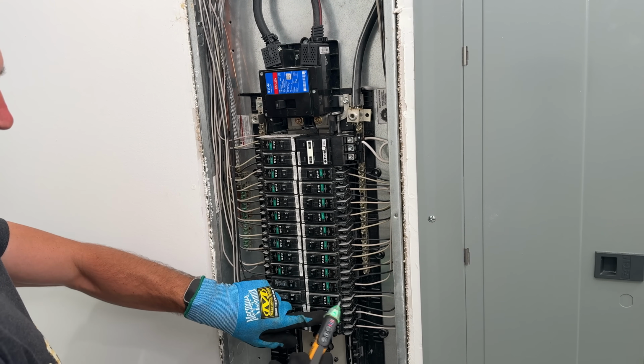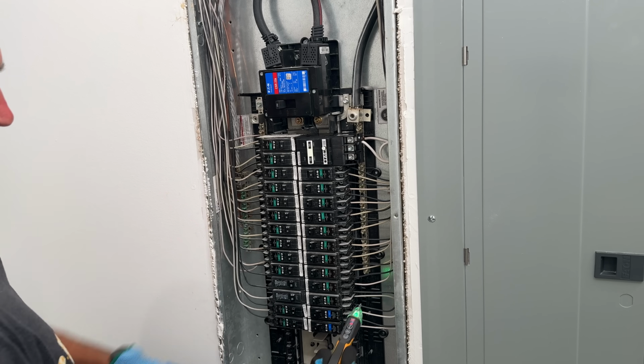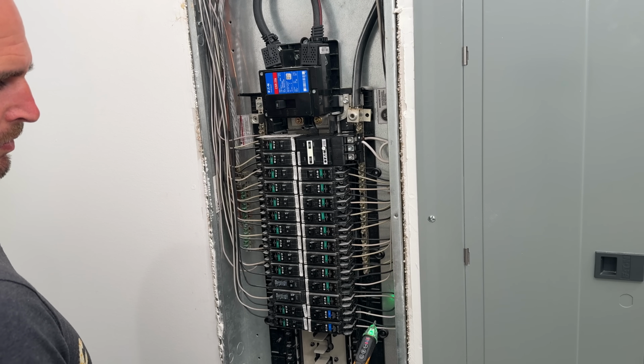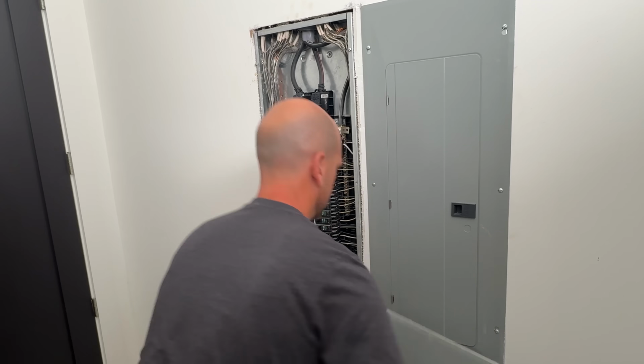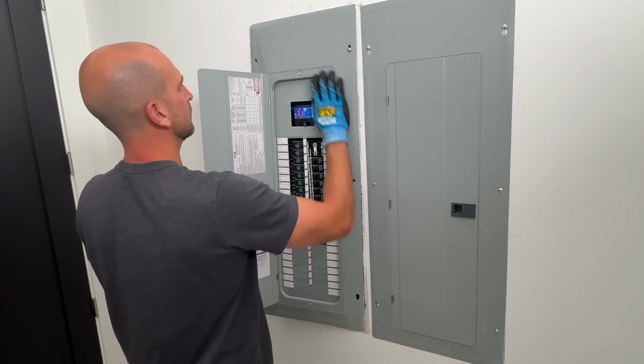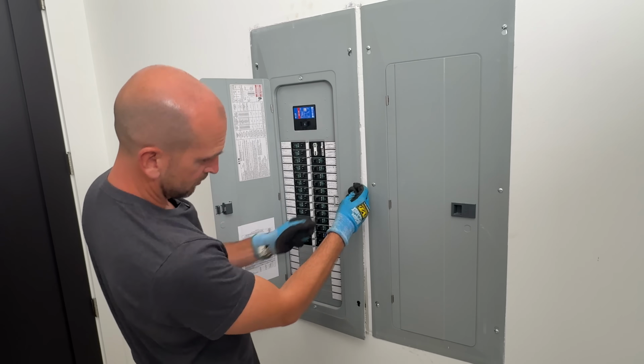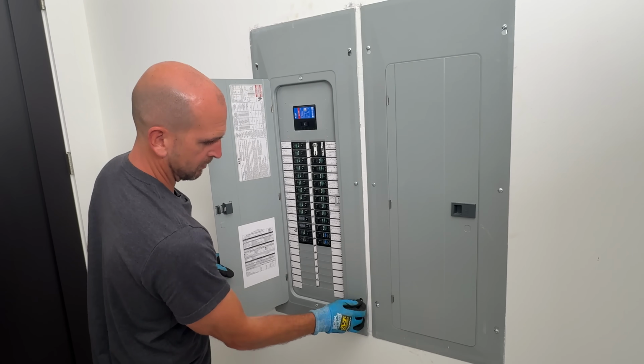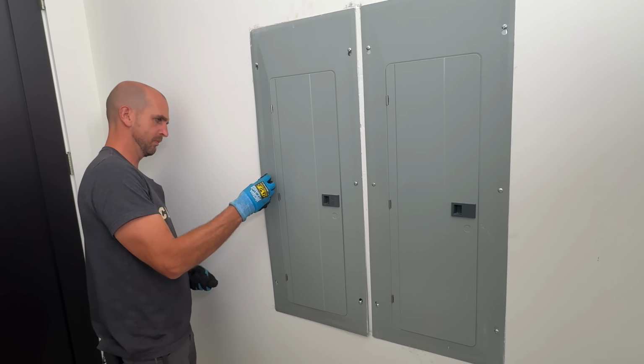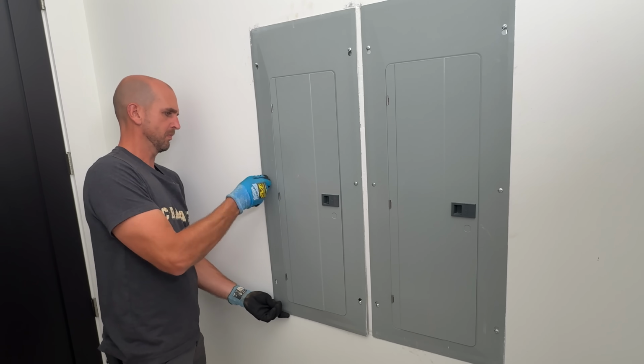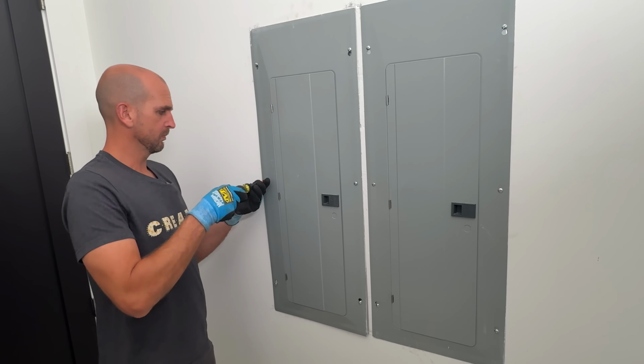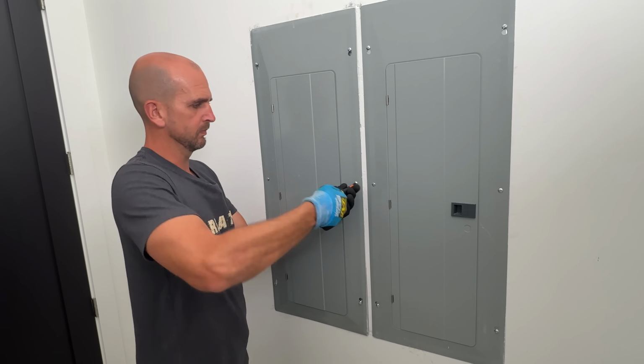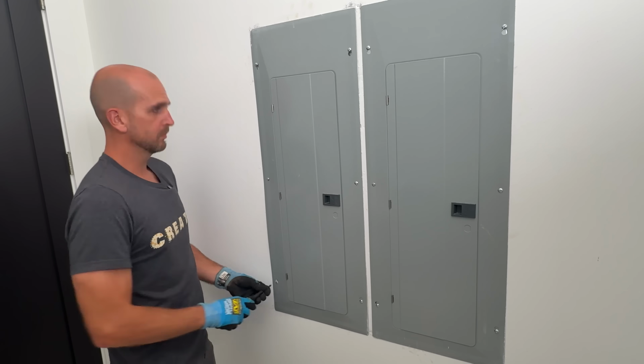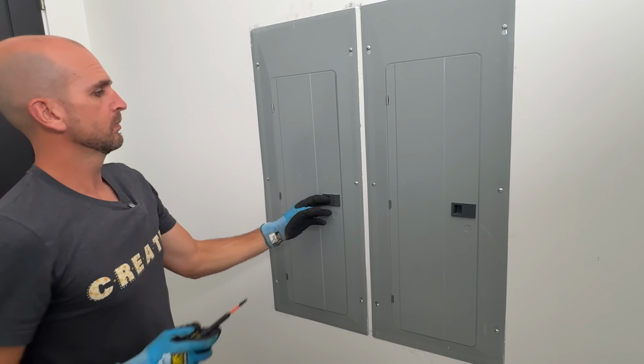Now I just turned the main breaker on and I want to test our work. I'll turn the 2 breakers that we moved on and confirm that we do have power at the hot black wires. Once that's confirmed, now you're ready to put on your modified cover, making sure everything's lining up, taking your time, and it is best practice to turn the main disconnect back off, so if the cover falls in, you just have fewer things that are live within the actual panel itself. Tighten everything up, and now we're done with our modifications.